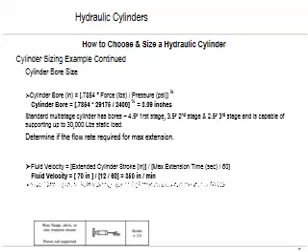These are some applications, like lift is 58 350 lbf, the maximum stroke is 70, and dump position is 12 seconds. Pressure set is 2400 psi. Flow rate is 25 gallons per minute. These are the requirements, and based on them we need to design the hydraulic system. This is the mounting accessory selected, and calculations like cylinder bore and fluid flow velocity. Finally, these are the things we calculate.